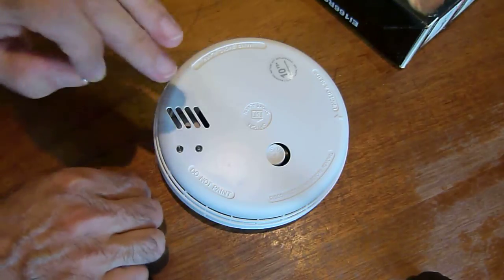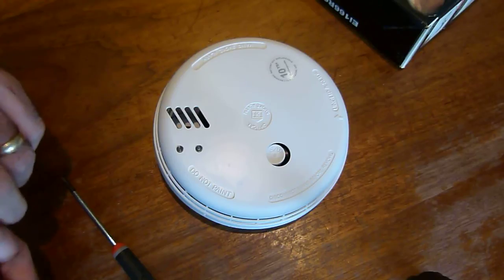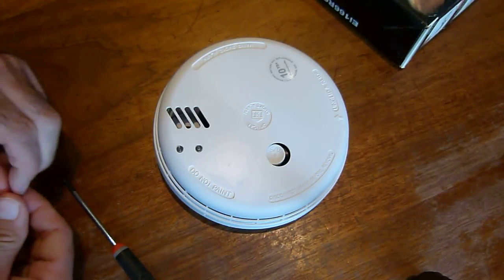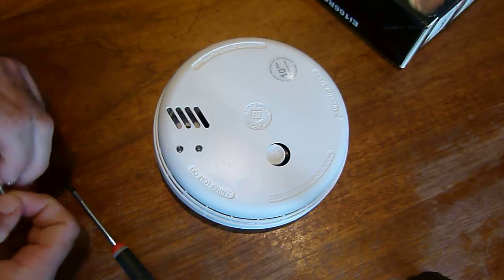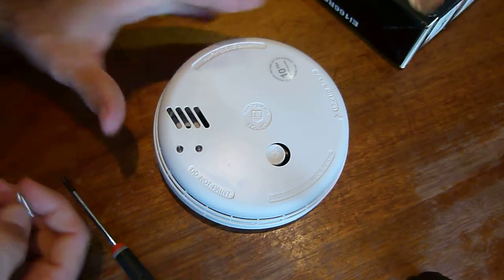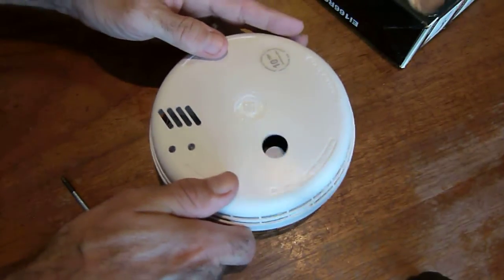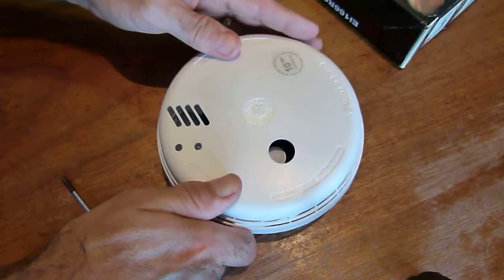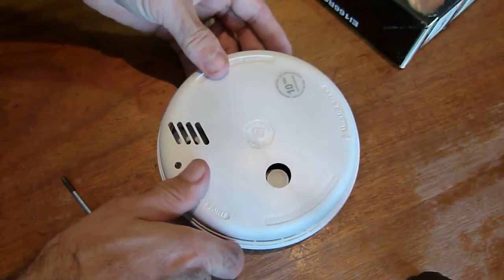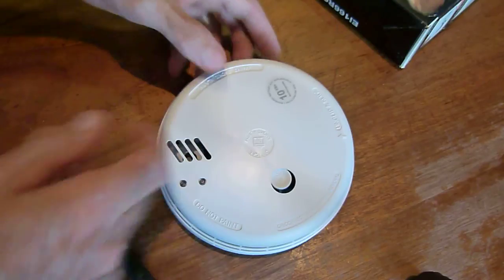There is nothing else that really goes wrong with this particular brand of smoke alarm. They're absolutely fantastic as long as you keep the bugs out. I'm going to pull them off every year or so just to blast the bugs out, because we have doors and windows open a lot due to the warm temperature, giving bugs more opportunity to get in. Brilliant smoke alarm — optical is the best. The ionizing ones in the tropics give too many false alarms, but with this brand we've had basically no false alarms apart from the odd bug getting past the net. Highly recommend.